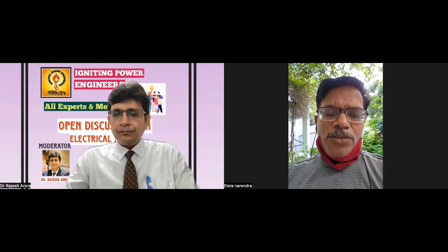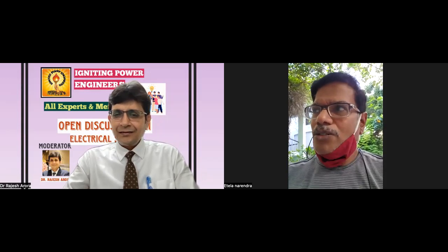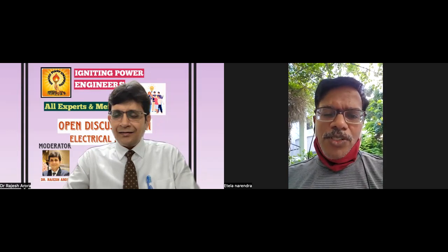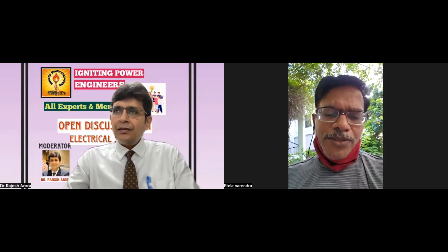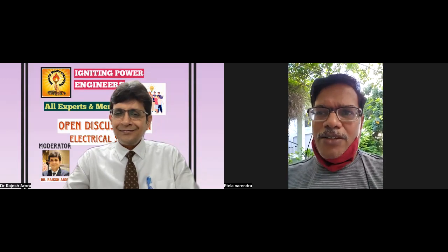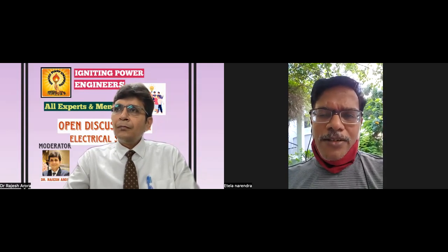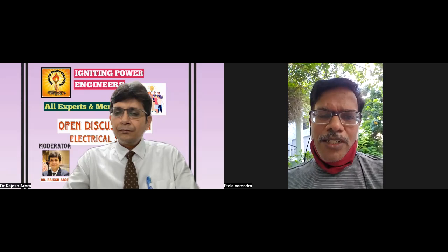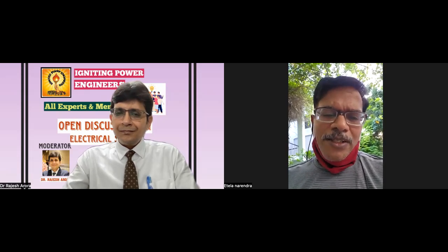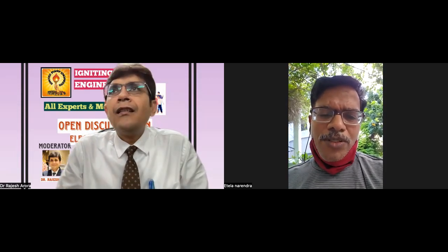Sir, you are muted. In the thunderstorm and rainy season, the transformer neutral was not correctly maintained. Because of that, there was a line fault that was brought into all the residential houses, wherein refrigerators and TVs all got burnt out. Even a few loads which were not in the supply also got burnt out. If I am correct, in my colony itself, not less than 2 to 3 lakhs worth of gadgets were spoiled. But after 3 hours, the Discom people came to the rescue operation and made everything pakka. They are saying that some high voltage had come. So this accountability needs to be transferred to the Discom people, and the awareness should be carried out by us, the technical people who did the work.